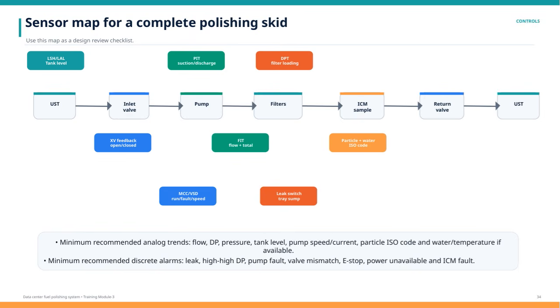We also track several important measurements through various sensors. Tank level sensors using LSH and LAL indicators, valve position feedback confirming open or closed status, suction and discharge pressure via PIT sensors, as well as flow and totalized flow with FIT sensors. Differential pressure across filters is monitored using DPT sensors to detect filter loading conditions. Particle contamination and water content levels are identified through ISO codes, providing insight into fuel quality. Additionally, a leak switch on the tray sump serves as a critical discrete alarm to detect any leaks promptly.